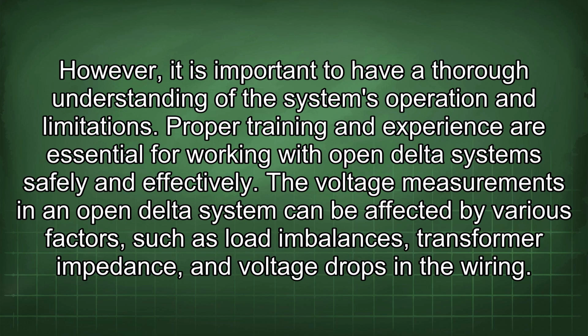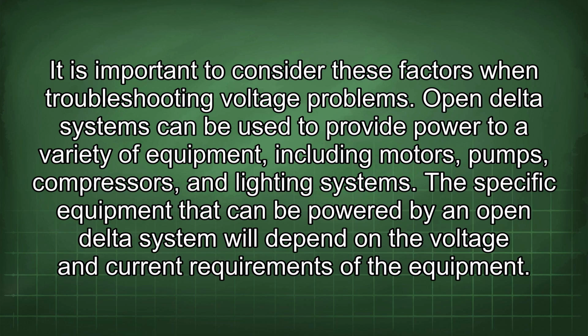The voltage measurements in an open delta system can be affected by various factors such as load imbalances, transformer impedance, and voltage drops in the wiring. It is important to consider these factors when troubleshooting voltage problems.